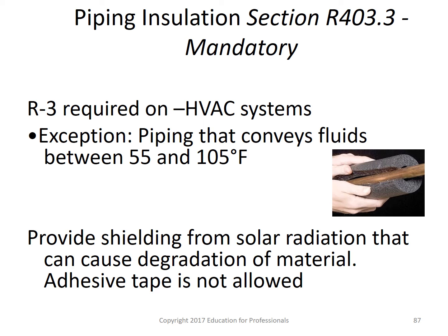And we'll move on to piping insulation and what is mandatory. And this is required, of course, R3 required on HVAC systems. They say with the IECC code there's an exception, piping that conveys fluids between 55 and 105 degrees Fahrenheit. But if exposed to weather, obviously protect from damage, including sunlight, moisture, problems that occur during equipment maintenance, and wind problems. In general, provide shielding from solar radiation that can cause degradation of material. And keep in mind that adhesive tape is not allowed.